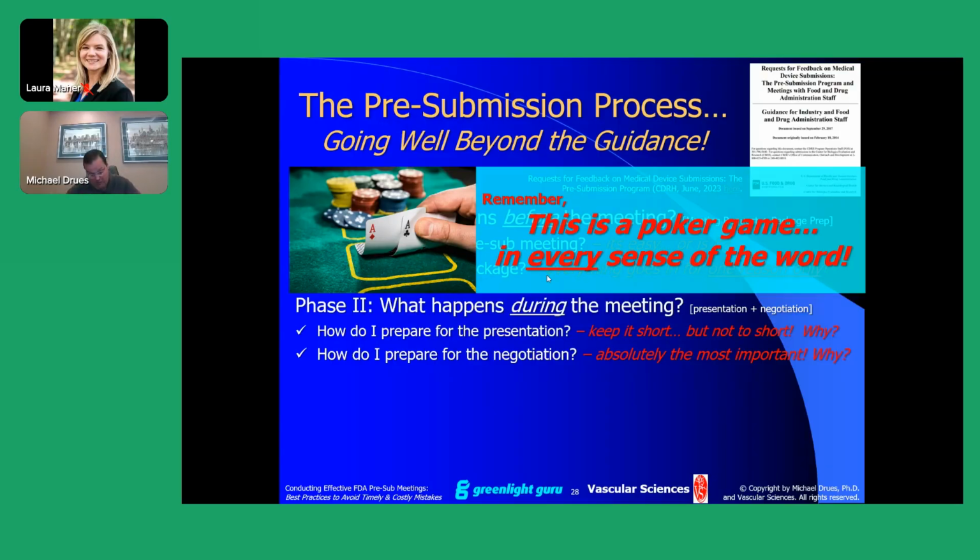And one of the things that I do with my customers, it's not on a slide, maybe I should add it, is before going to the FDA with a pre-submission, or I do this with file submissions as well, the company will ask me to come in and put my FDA reviewer hat on temporarily and read their pre-sub package, sit through their pre-sub presentation, and if I can be a bit blunt here, bash the hell out of it. Because the idea is, if there's going to be a weakness or if the company's going to make a mistake, better for them to do it in front of me. After all, what do I count? I don't matter, than doing it at the FDA where it really does matter.